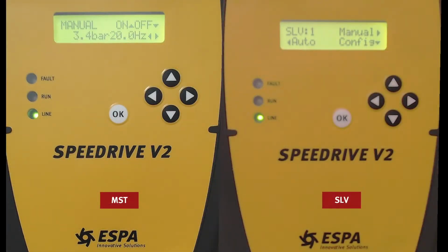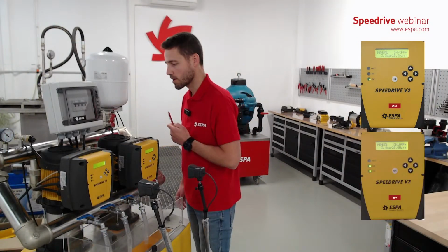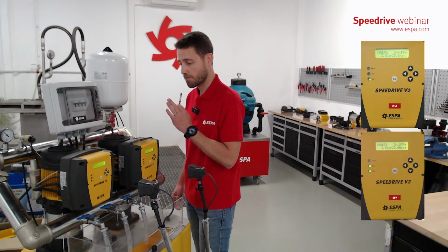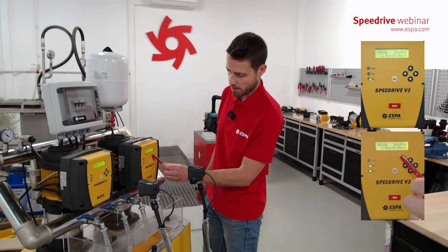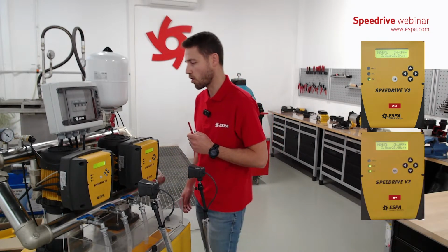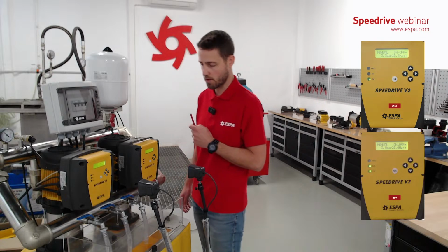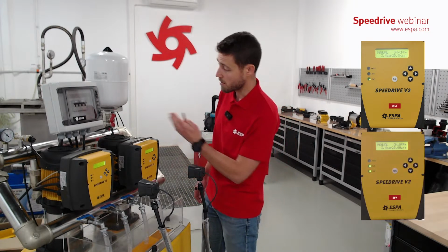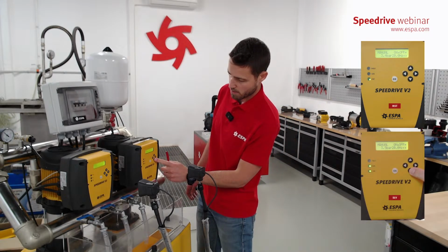We can do the same step with the slave pump: turn it on and have a look at the fan. As the fan is moving at 20 Hertz, it goes slow enough to see if it turns properly. It turns clockwise, so we can turn it off.